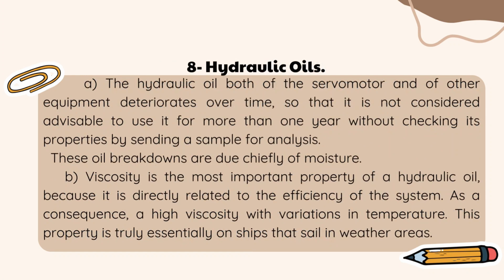8. Hydraulic oils. A. The hydraulic oil, both of the servo motor and of other equipment, deteriorates over time, so that it is not considered advisable to use it for more than 1 year without checking its properties by sending a sample for analysis. These oil breakdowns are due chiefly to moisture. B. Viscosity is the most important property of a hydraulic oil, because it is directly related to the efficiency of the system. As a consequence, it must maintain a high viscosity with variations in temperature. This property is truly essential on ships that sail in cold weather areas.